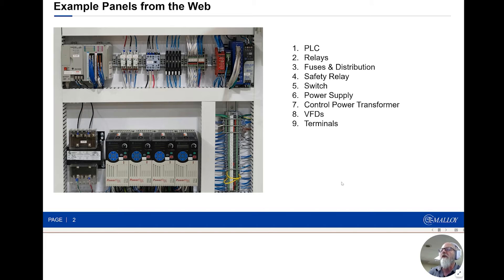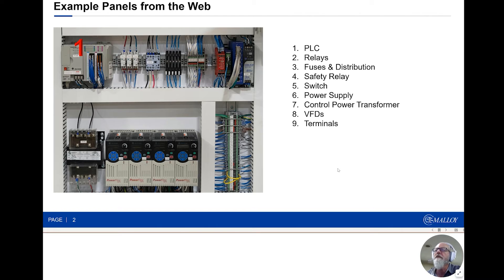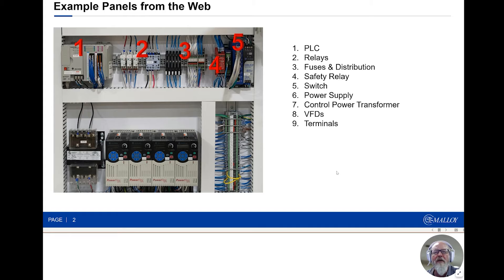This is the first example of a control panel with a PLC and drives. We're going to start going through the components. The first one, obviously, is the PLC — think of the programmable logic controller as the brains of the operation. Then we have relays and contactors, fuses and distribution. We have a safety relay — not always present, because not all systems need safety controls. Then an Ethernet switch, primarily to allow the PLC to communicate to the drives. Some systems will also have HMI and remote I/O communicating over Ethernet, depending on the protocol and PLC type.